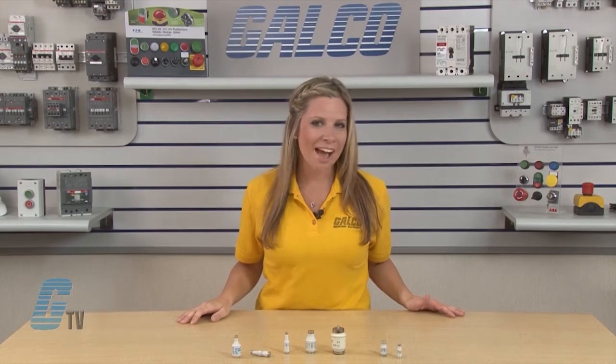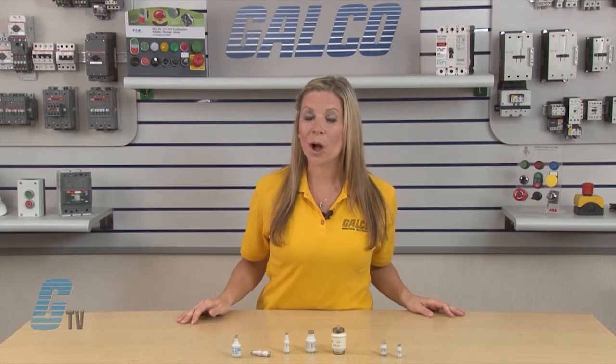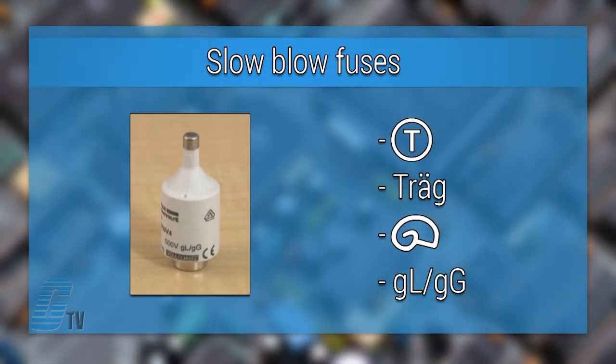Milk bottle fuses also have different tripping characteristics. Fuses with a time delay, also called a slow blow fuse, can be marked with either the letter T, Träg, a snail symbol, or GLGG.